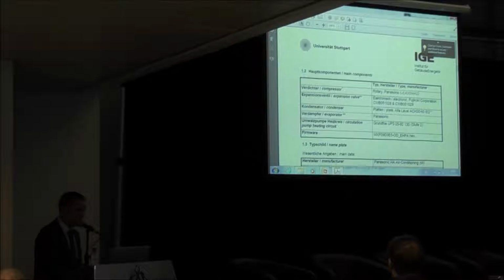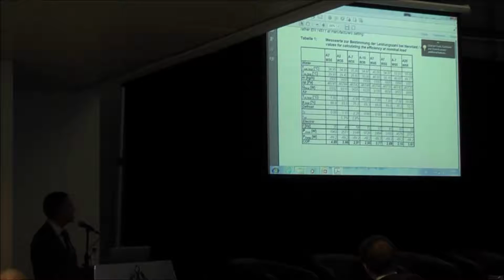So it gives a brief description of the unit. It shows photographs not only of the unit but the nameplates and certain elements of the unit. It details the heat exchangers, the compressors, etc. For this unit, I don't know if you can see towards the bottom, it's rated at 4.74. So that's a COP of 4.74. For every kilowatt of energy we're putting into the unit, we're getting 4.74 kilowatts of heat out. The test criteria they tested to are all these different conditions here, because all over Europe they'll have different testing criteria. So for air at 7, water at 35, which we had as 4.74, it actually came out at 4.89, slightly better.